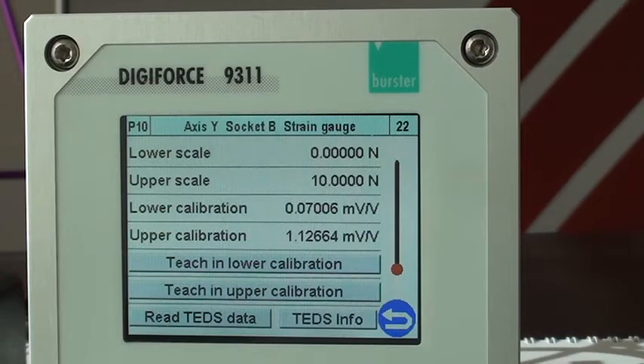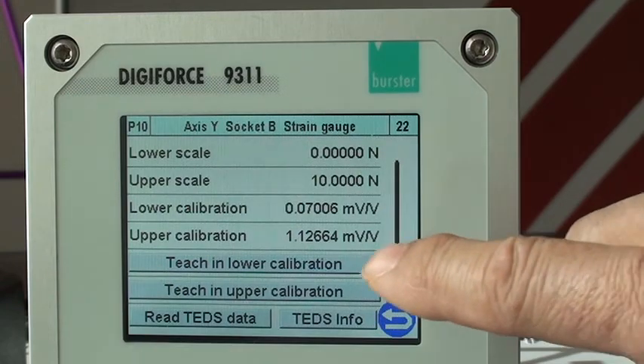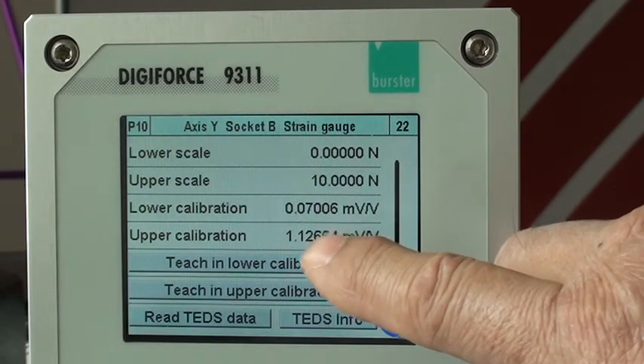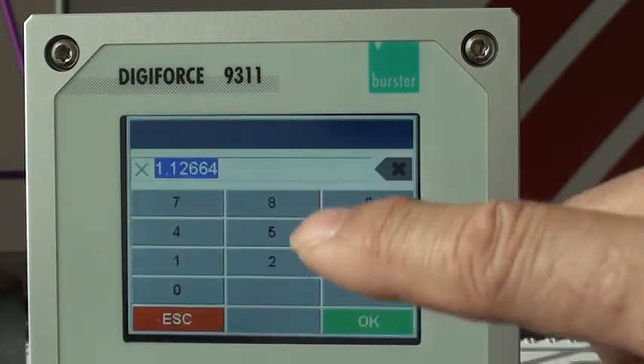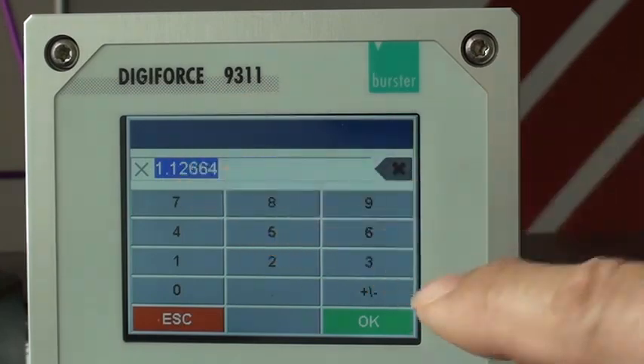Because this is a load cell, we do not have a calibrated load that exactly exerts the force to be able to teach in the upper calibration. We're going to use the data sheet that comes with the load cell. In order to enter this data, we have to add the lower calibration number that we just finished measuring. We add it to the calibration data sheet, and the sum of the two numbers will be entering in the upper calibration. So when we select, we enter the sum of those two numbers in here.